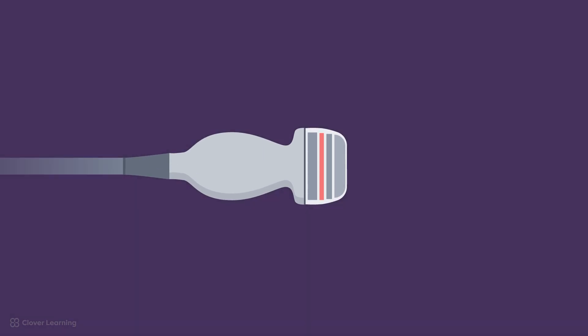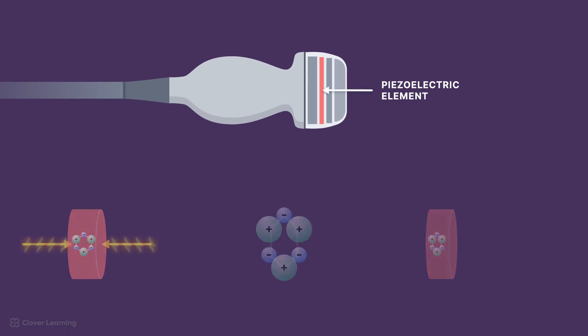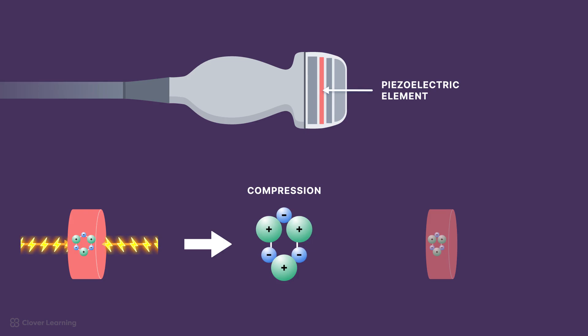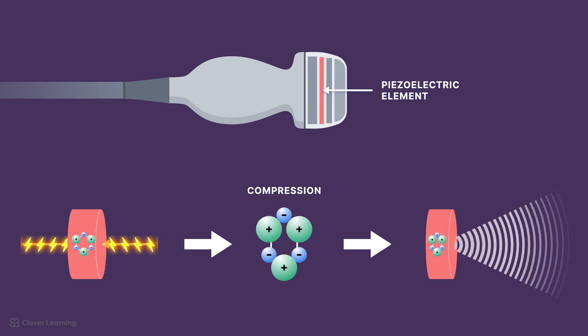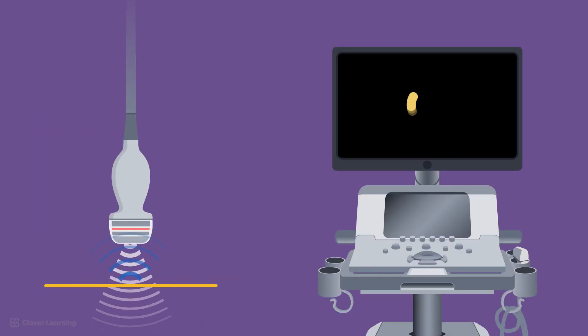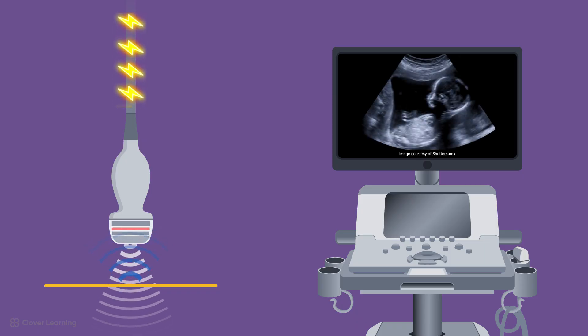The transducer crystal has piezoelectric properties and is the most critical component of an ultrasound transducer. Piezoelectric properties means that when electrical energy hits the crystal, it expands and contracts in thickness, which causes compression and produces sound waves that travel into the body. When echoes return, the crystal vibrates again, converting those sound waves back into electrical signals that create an image.